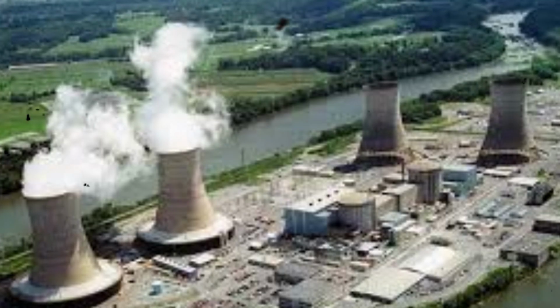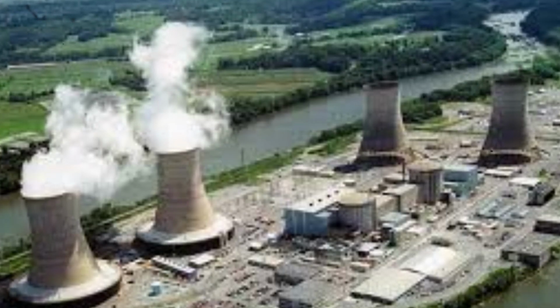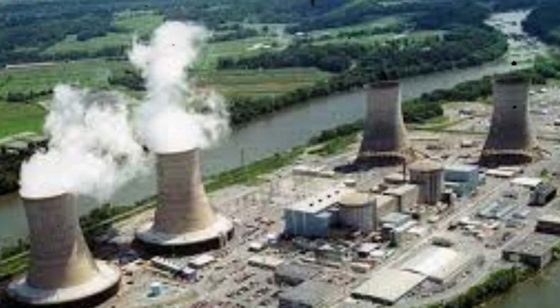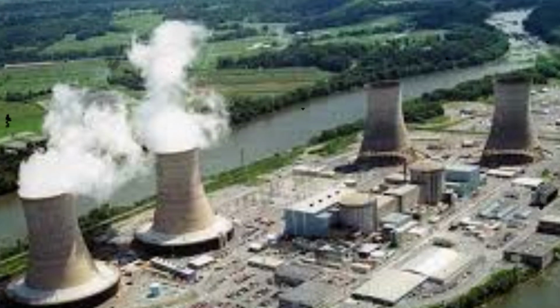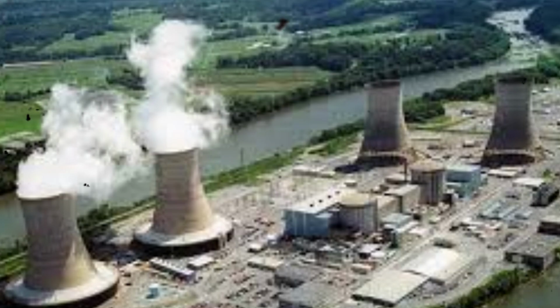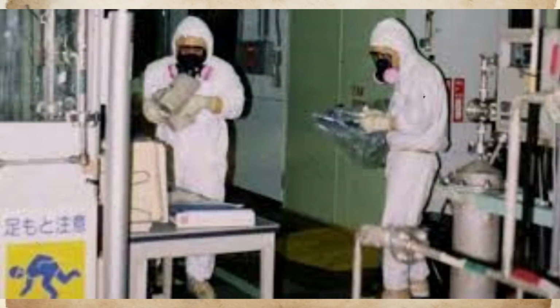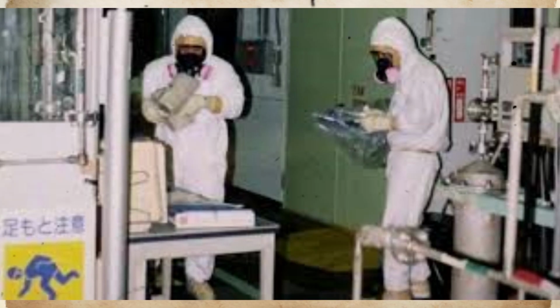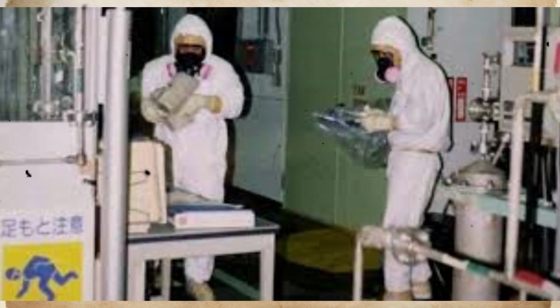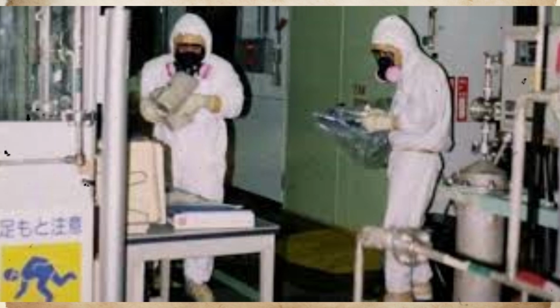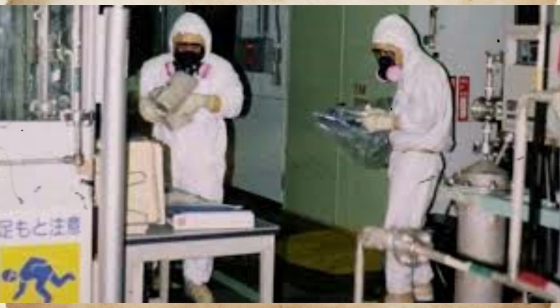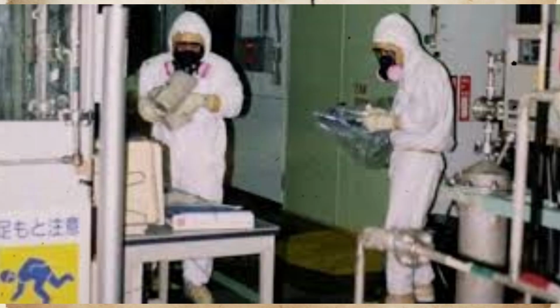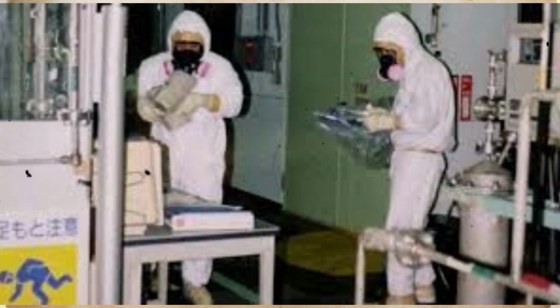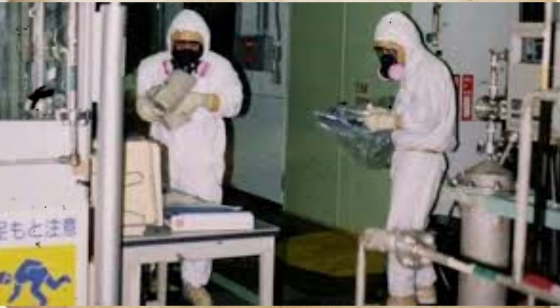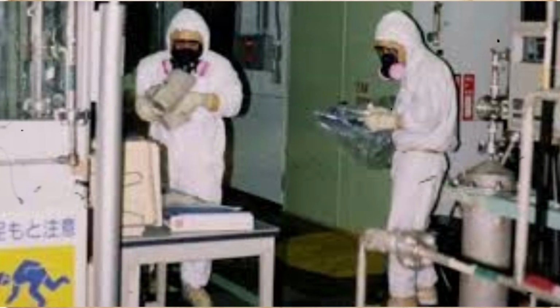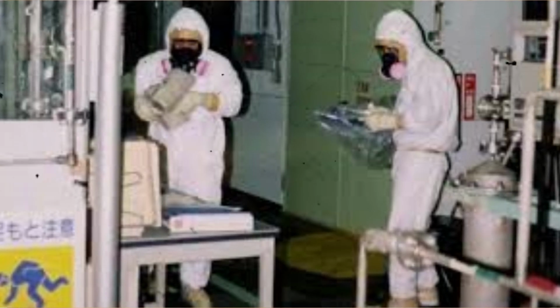The progression toward fuel melting in Unit 1 was essentially irreversible once initiated, but operators lacked any direct indication of these processes. Containment radiation monitors provided some evidence of fission product release, but specific core damage assessment required interpretation of multiple indirect indicators that were difficult to evaluate under emergency conditions. Temperature instruments within the reactor vessel had limited range and accuracy under severe accident conditions. Hydrogen concentration measurements were not available in the reactor building atmosphere.